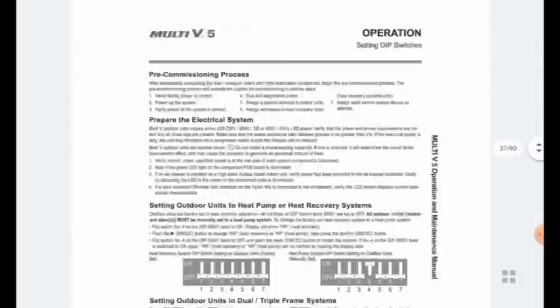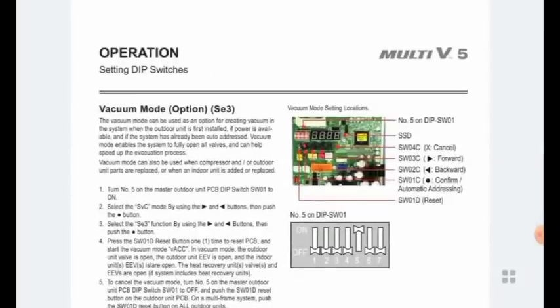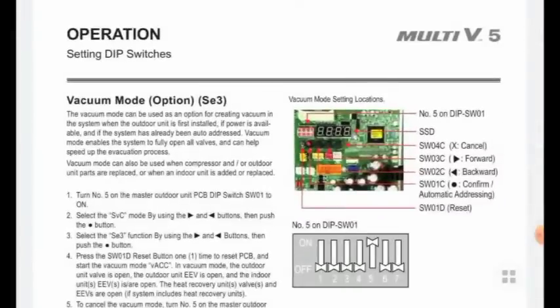When doing the vacuum, we have to make some settings first. In the DIP switch, number 5 should be ON — this setting is for the master unit only, not for the slave units. Only for the master unit we have to put DIP switch number 5 ON. After that, press the DIP switch SW01D once to reset for vacuum mode.